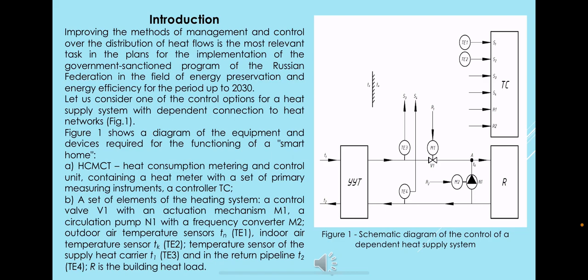HCMCT is the heat consumption metering and control unit containing a heat meter with a set of primary measuring instruments, a controller TC, a set of elements of the heating system, a control valve V1 with an actuation mechanism M1, a circulation pump N1 with a frequency converter M2, outdoor temperature sensors, indoor air temperature sensors, and other parts of the system shown in Figure 1.